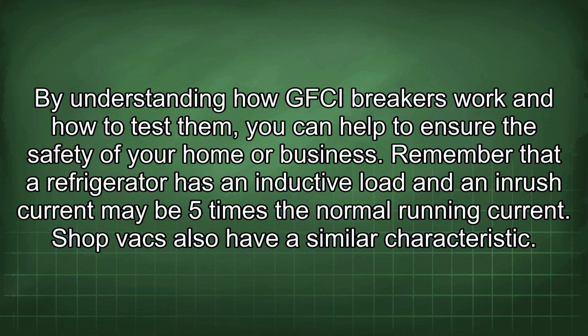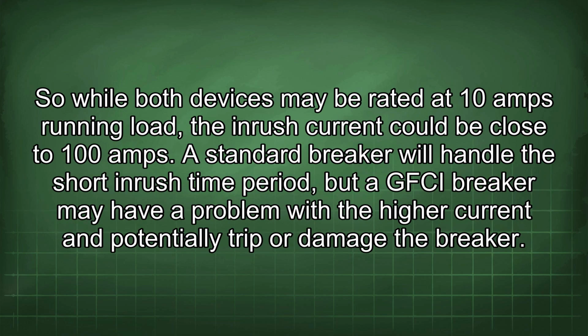By understanding how GFCI breakers work and how to test them, you can help to ensure the safety of your home or business. Remember that a refrigerator has an inductive load and an inrush current may be 5 times the normal running current. Shop vacs also have a similar characteristic. So while both devices may be rated at 10 amps running load, the inrush current could be close to 100 amps. A standard breaker will handle the short inrush time period, but a GFCI breaker may have a problem with the higher current and potentially trip or damage the breaker.